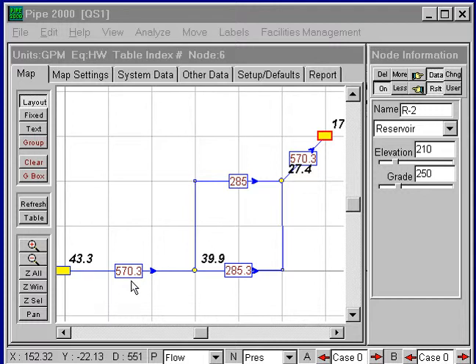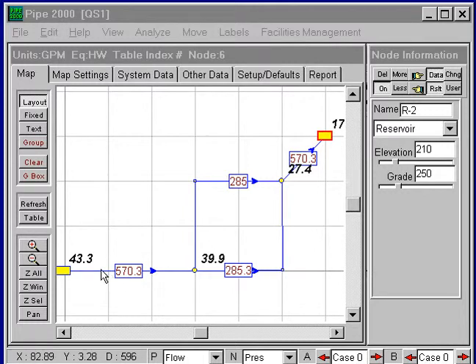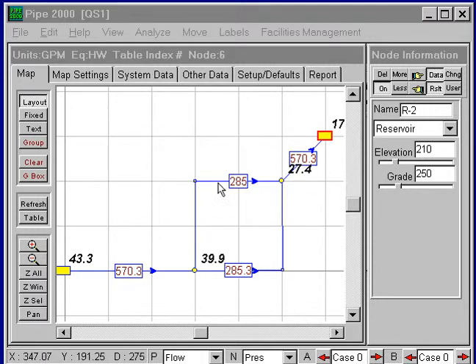The results shown here were for a simulation when the pipe was new. The roughness in the steel pipe or ductile was 130, and these PVC pipes had 140.